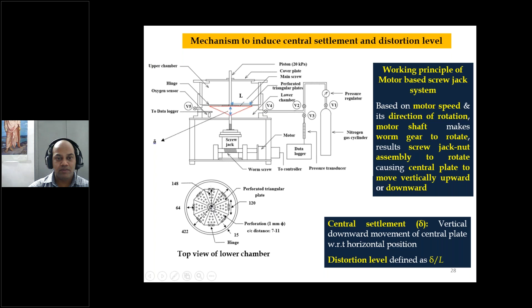Then coming to the measurement of gas permeability. First of all, a specific nitrogen gas pressure is applied into the gas chamber of the test apparatus by opening valves V1, V2, V3, V4, and valve V5 is closed. When a particular gas pressure, that is 5 kPa, is reached, valves V2 and V1 are closed.